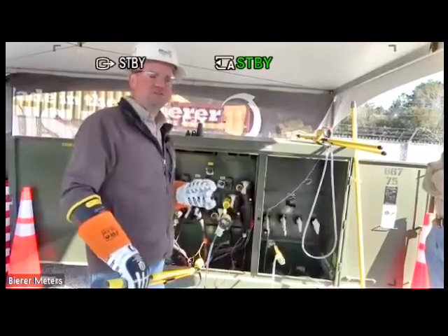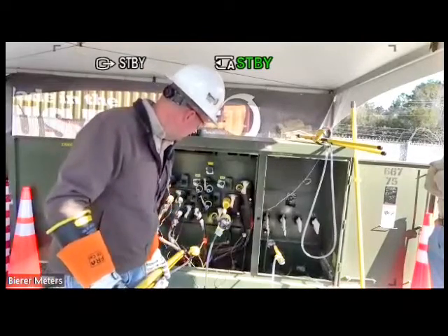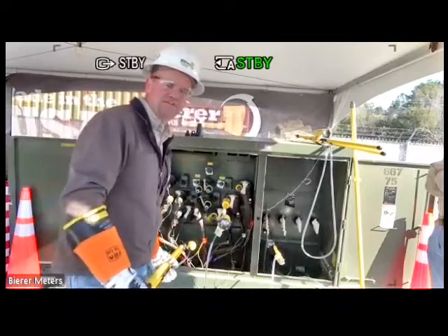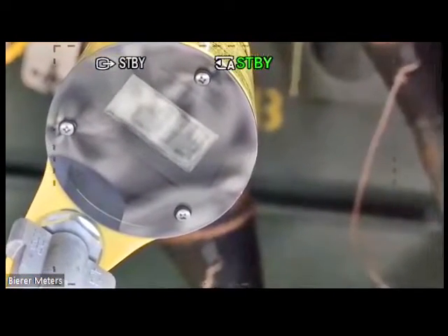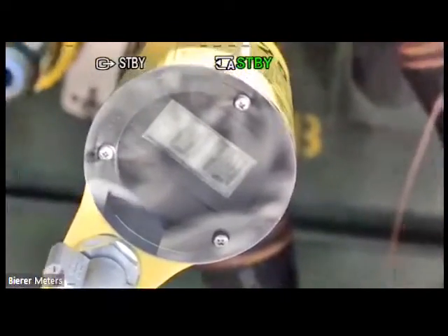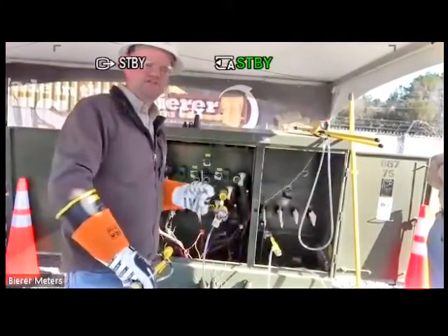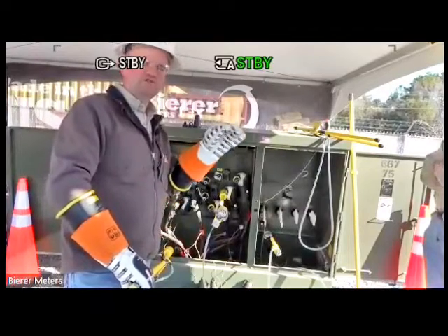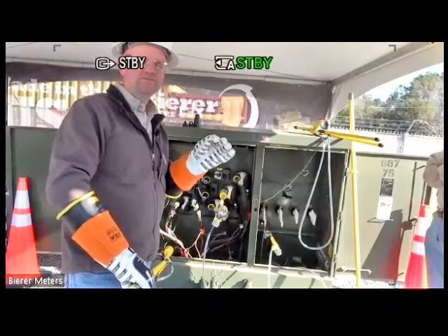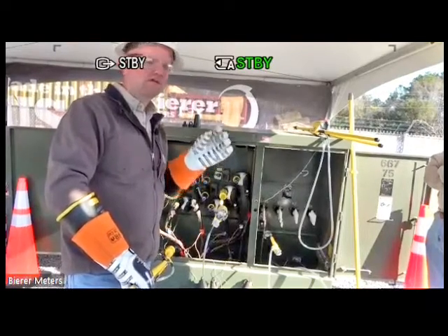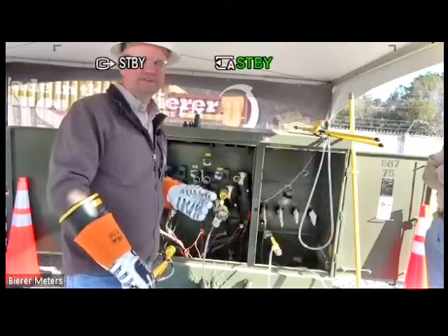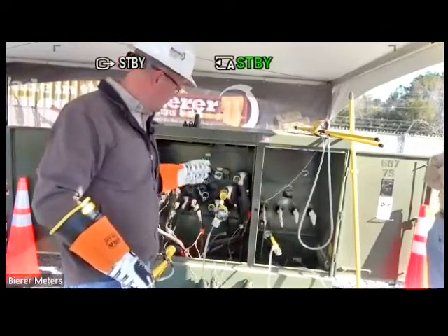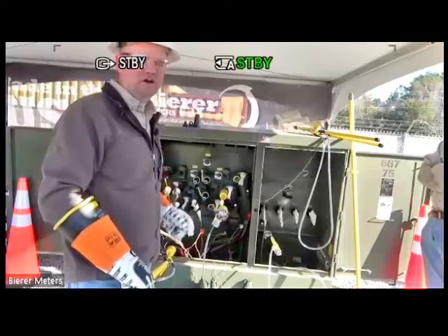That's what you should expect to see. If you had a high impedance fault, what you would see is this number may go up to some value. So like it's starting to bounce around. I'll get this number to bounce around a little bit. I'll try to do my best on this, but it's hard to duplicate a pinhole. But maybe it goes up, it goes down, it goes up, it goes down, it goes up. And basically what it's trying to do is charge that cable up to some potential. Maybe it's 6 kV, 7 kV, whatever that number may be. And then it tries to discharge, or it does discharge. It actually blows through that little pinhole or high impedance fault, wherever that may be. Maybe it's to the concentric, whatever. It blows through there, discharges the cable. It tries to charge it back up. So it just sits there and oscillates back and forth. So you'll see that number bouncing around, up and down, up and down. That's a high impedance fault.